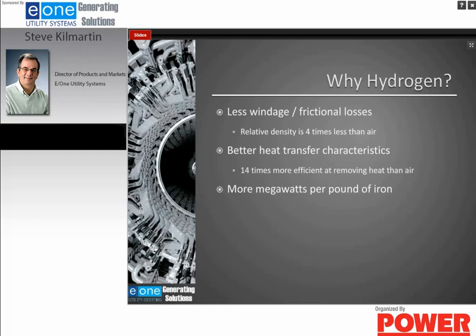Why hydrogen? One of the reasons is that hydrogen has less windage losses, less frictional losses. Hydrogen is 4 times less dense than air. What this means is that you can create more megawatts with less horsepower. It is not as difficult to turn the generator with hydrogen versus air. Also, hydrogen has better heat transfer characteristics. It is 14 times more efficient at removing heat than air is. And as I mentioned, when you increase megawatts, you not only increase the size of the generator, but you also create more heat. Again, more megawatts means more pounds of iron. The generator gets larger.